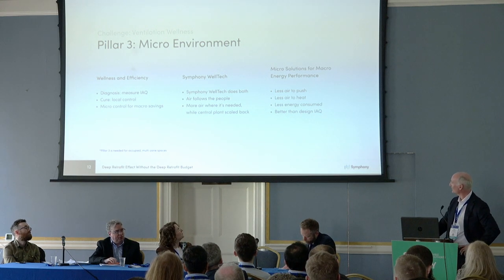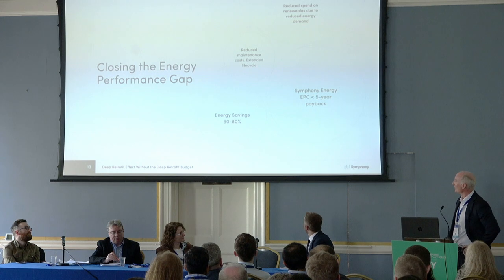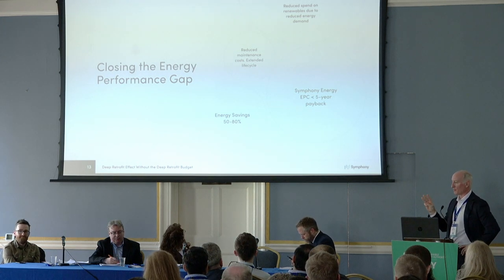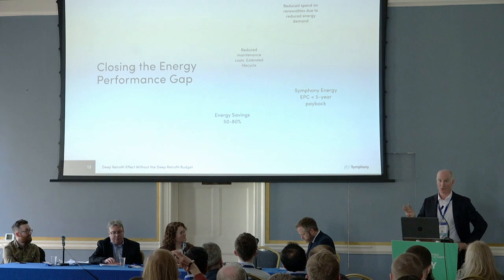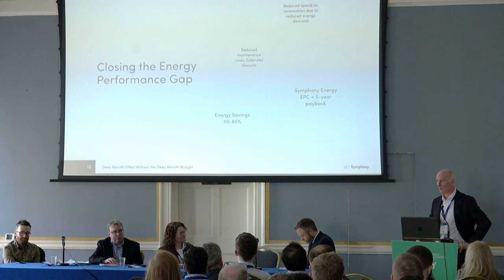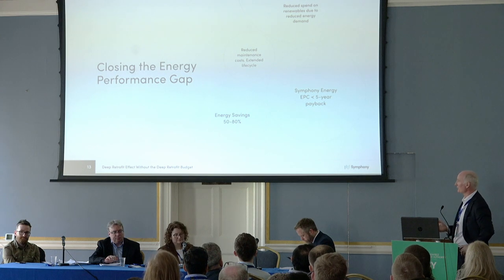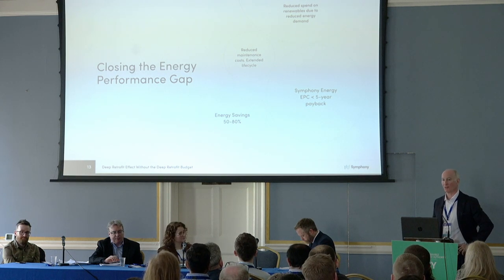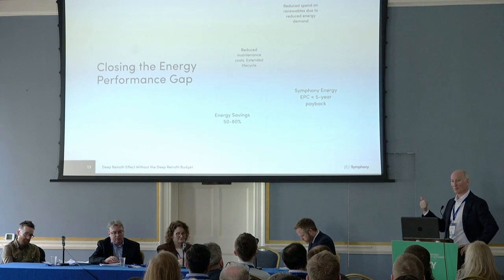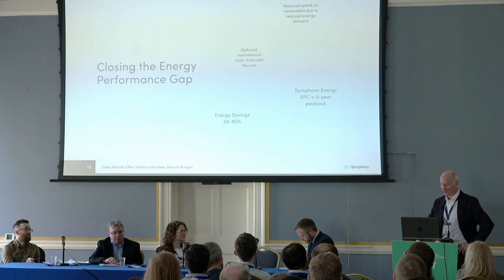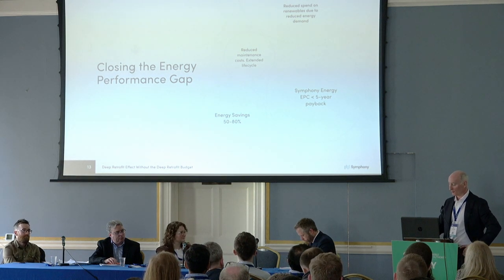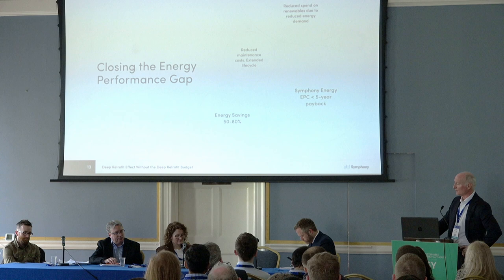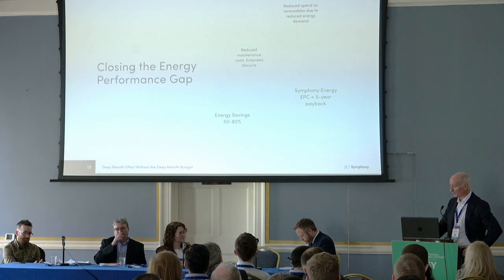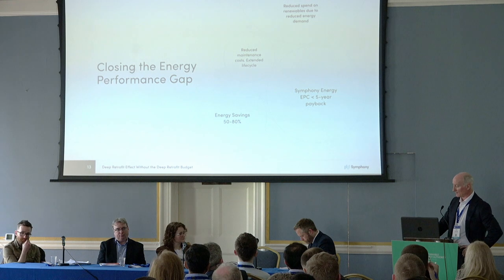Less air to heat, push, and better than design IAQ. Ultimately, when you tackle these three challenges square on, whatever way you do it, if you really tackle them—and we believe we manage to—you're looking at savings of between 50 and 80%. It doesn't have to be an old building to get 80%; we're actually finding it's the newer buildings. We tend to be brought to newer buildings because people figure they've got other things to do in older buildings, but these are the kind of savings you get even on newer buildings, with a 3 to 4 year payback at today's prices, or 5 years at 2021 prices.